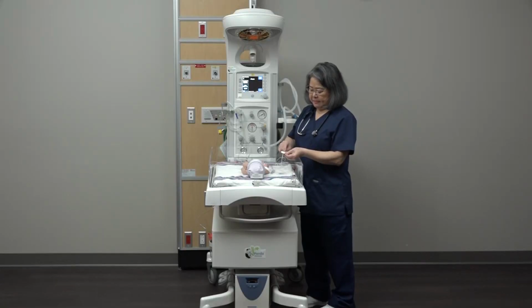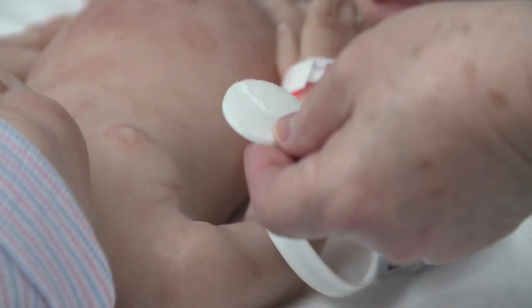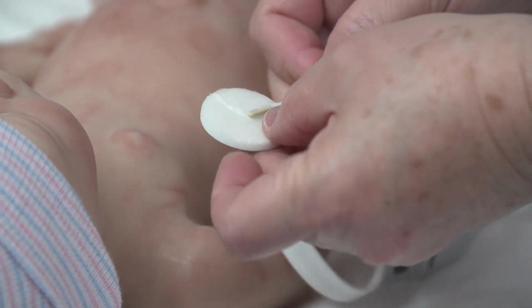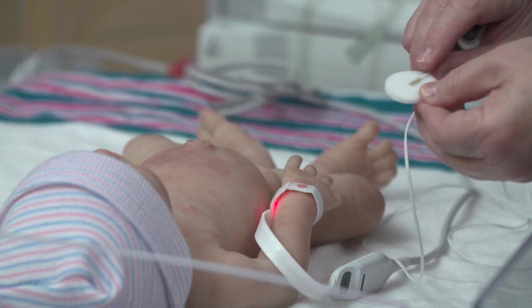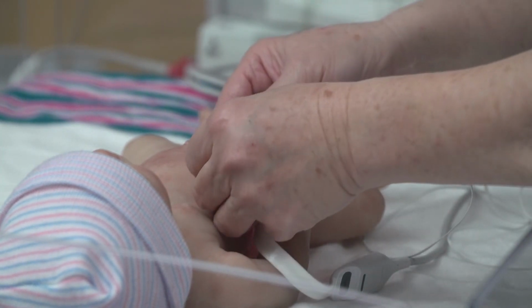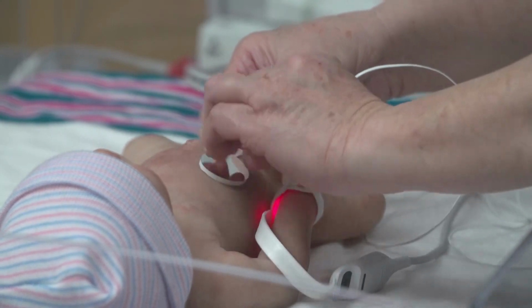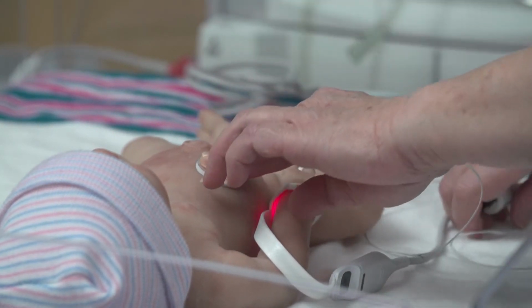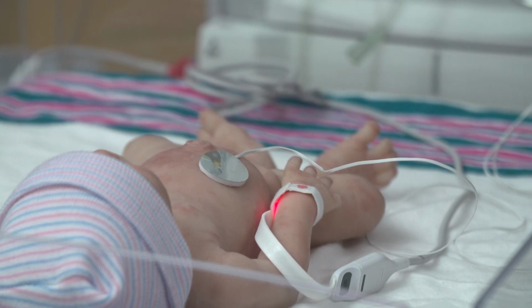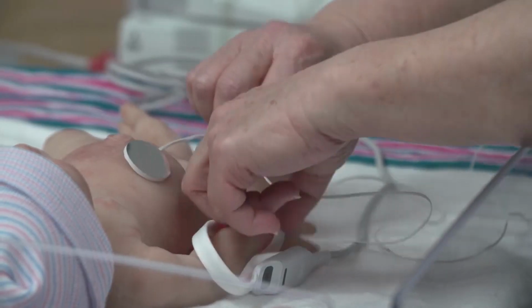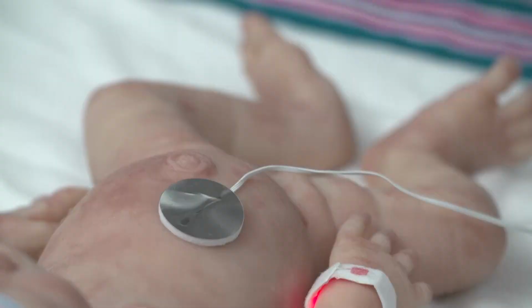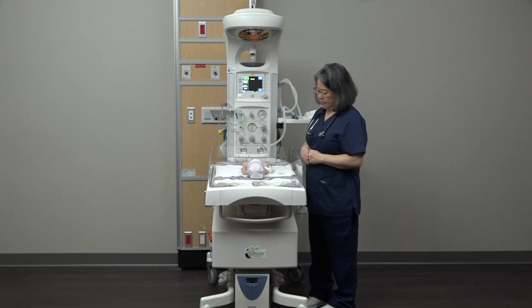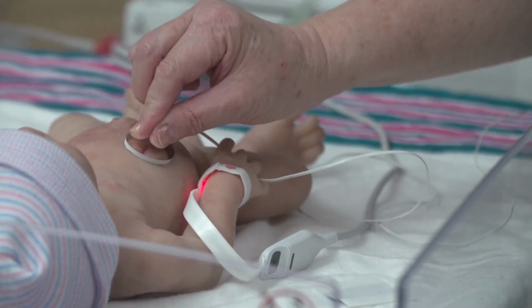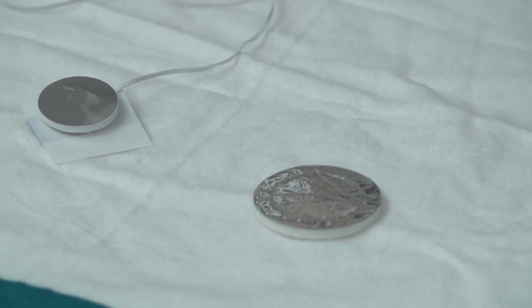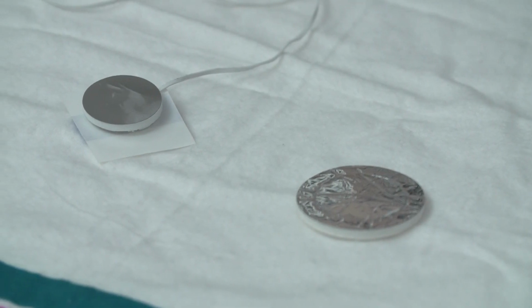Here are some tips for placing a temperature probe on a baby. Place the temperature probe securely on the reflective patch, and then securely to the patient's skin, pressing and holding to ensure good contact. It can be placed on the back or abdomen, depending on if the patient is prone or supine. Alternately, consider placing on the axilla. The reflective patch should be reflective foil side up. Both the disposable and reusable temperature probes should be placed this way. Do not use the temperature probe without the reflective patch.